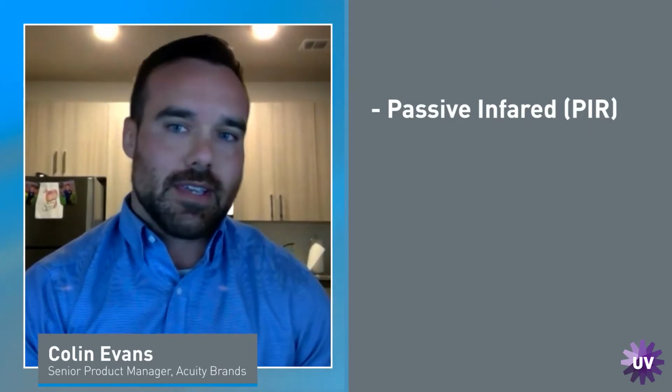So Ron talked about occupancy sensors. So that's a physical component. That's a device that's looking for that space to be occupied. There's different technologies behind that. The most common is called passive infrared. That's looking for body heat. That usually requires a large motion, so someone walking through a space for that to be seen. One caveat to that is it's line of sight only.